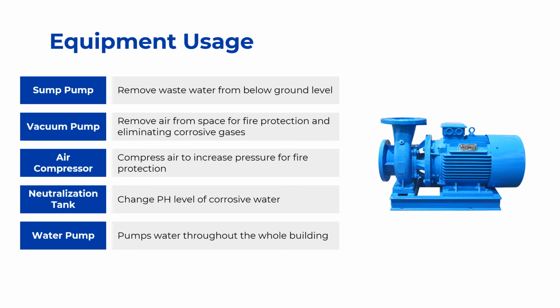You then have an air compressor, which compresses air to increase the pressure. It's either for fire protection or for eliminating any other odors or corrosive gases. Then you have a neutralization tank, which changes the pH level of corrosive water. Since this is an electrical and computer engineering building, they might need neutralization tanks in certain labs. Then, lastly, you have a water pump, which pumps the domestic water, either hot or cold, throughout the whole building.